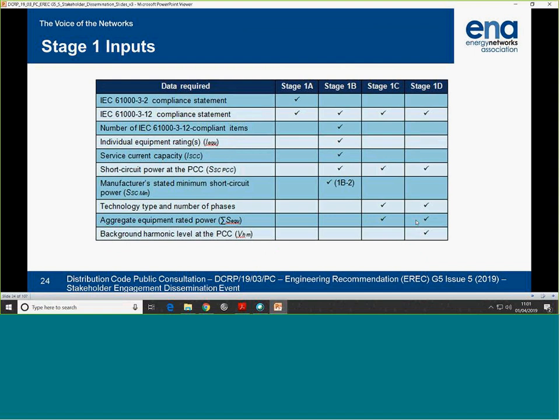All the values, the inputs to these calculations, then basically move across from left to right, from 1A to 1D. You're using more information, and the level of information required is increased. 1B, 1C, and 1D all require knowledge of the short circuit capacity of the system. And you get to the final stage, as I said, background harmonic level of the limiting harmonic.